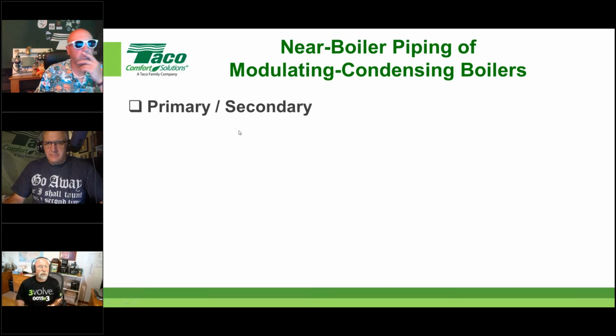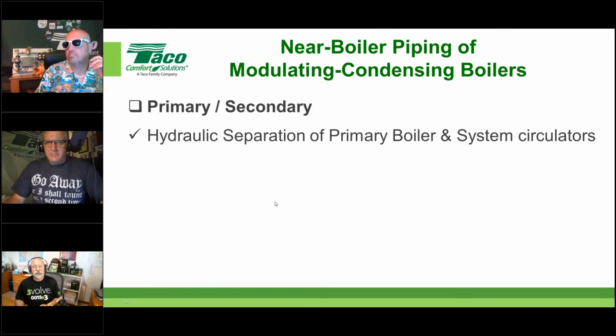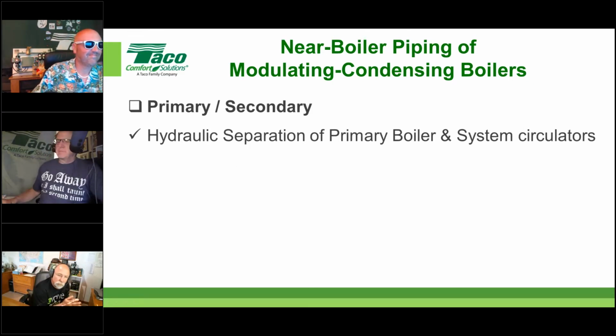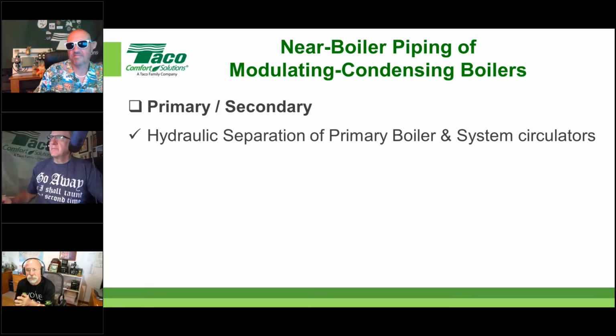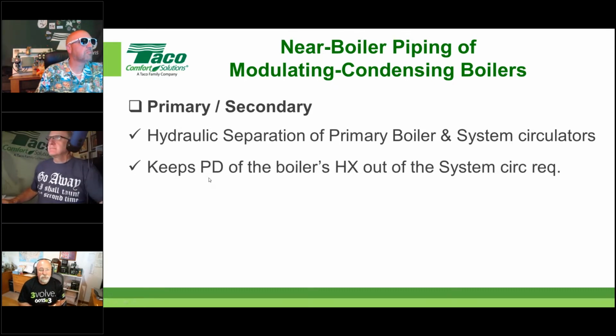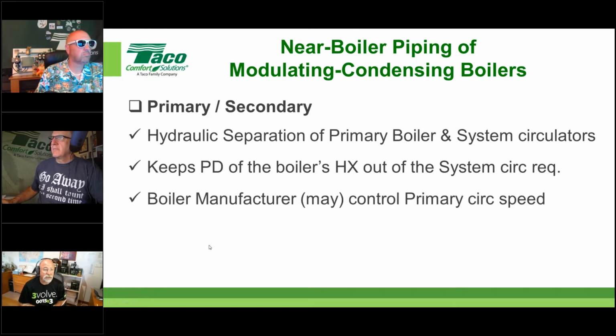The whole idea and the concept about primary, secondary is to get this thing called hydraulic separation. What we're trying to do is make sure the boiler circulator never affects the system circulator or vice versa. It gives us that good separation where the two can operate independently of each other. Okay. What we're trying to do is make sure that if it's done correctly, the pressure drop of the boiler's heat exchanger never has to be taken care of or considered by the system circulator. Okay, so all the boiler pump has to do is worry about its heat exchanger and a little bit of incidental piping. Then the system pump, all it has to worry about is what's within the system, and the two will never talk to each other if it's done correctly, and we'll emphasize that as well.